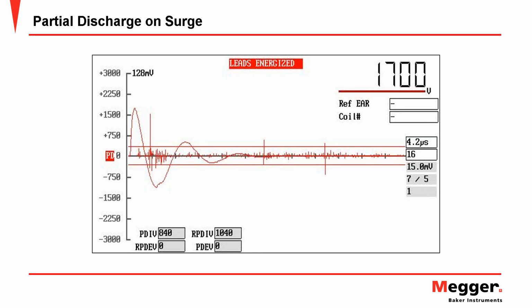One other thing I'd like to point out about surge testing, and our DX is capable of this type of testing, is looking for partial discharges that occur within insulation. So surge testing can excite internal ionization if there are voids in the insulation internally that go unseen. And this is another failure mode that we need to be concerned about for high voltage motors, but also for low voltage motors that operate on variable frequency drives. Because of the rapid switching rate, ionization can occur internally, producing chemically active gases that attack the insulation internally and can also lead to turn-to-turn failure. So quantification of partial discharge is also potentially an important mechanism that we have to evaluate during the surge test.